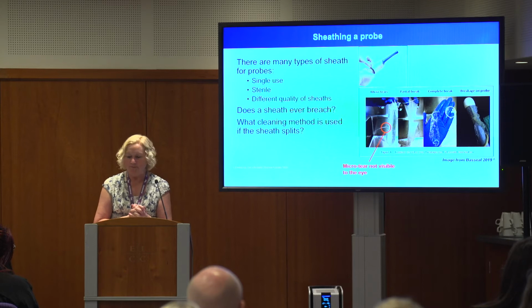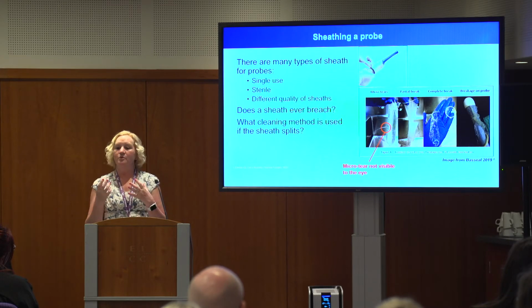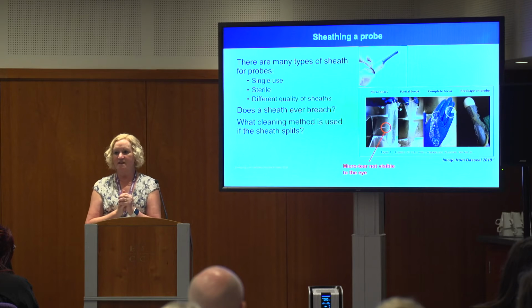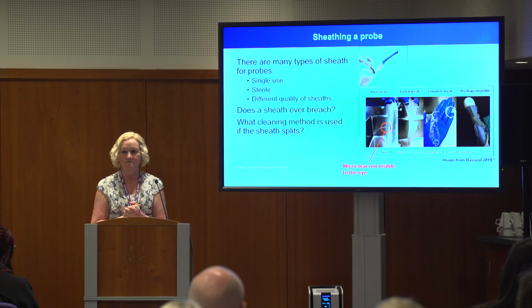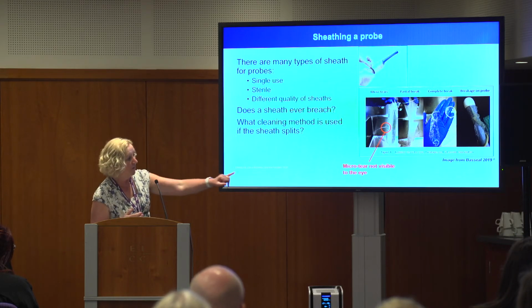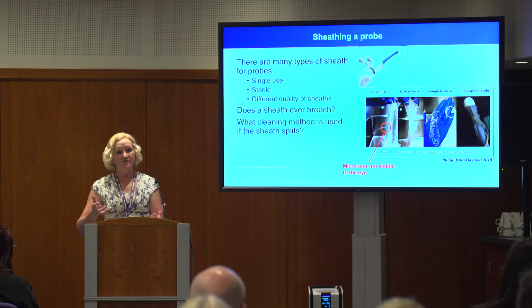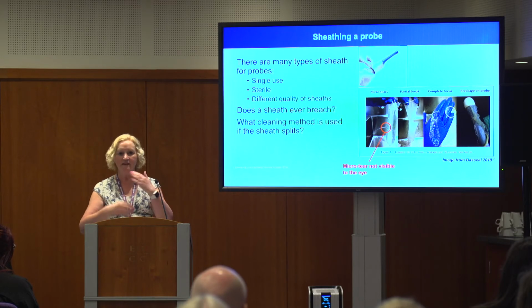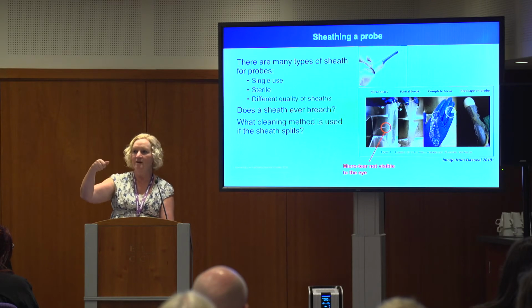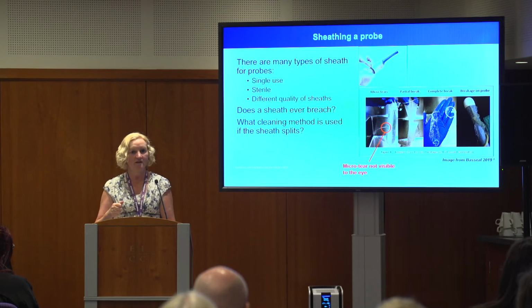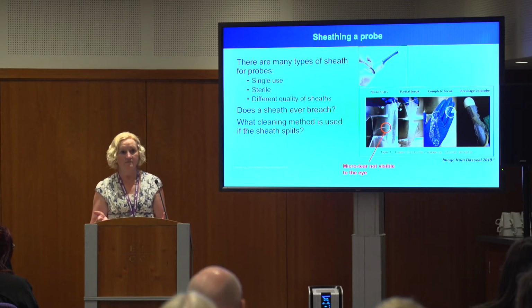Talking about sheathing. When you talk to a sonographer, most sonographers say it's very rare for a sheath to break. It might be, but how do you check it? How do you check that a sheath hasn't broken? If you've got a micro tear, you wouldn't see that unless you filled it up with water afterwards. You haven't got time to do that. You're in a busy clinic, going patient after patient. You haven't got time to fill each sheath up and check to see if there's any water leaking. You probably haven't even got a sink in there to fill it up with.